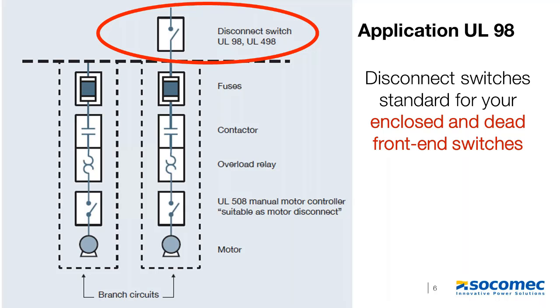430.109 of the NEC, which describes the disconnect means for motor application and defines how disconnect products are intended to be used and installed. So you need a disconnect means, branch circuit short circuit protection device, motor controller, motor overload protection device, and a manual motor controller suitable as a motor disconnect. So with each of these, NEC requirements come with different certifications per the device. So in today's webinar, we will be focusing on the UL98 and the UL508 standards.